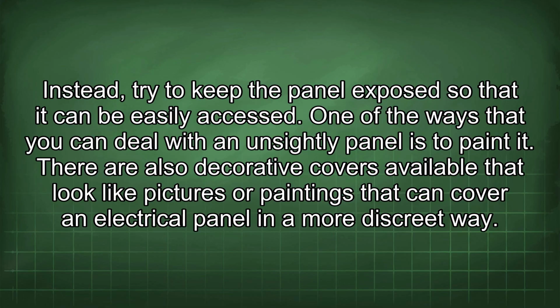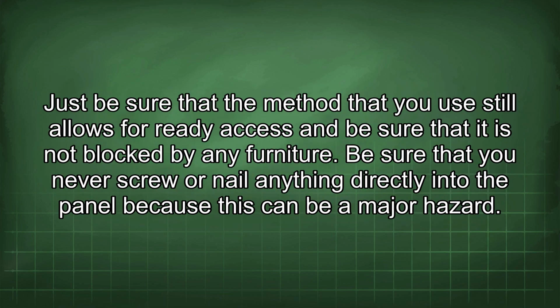One of the ways that you can deal with an unsightly panel is to paint it. There are also decorative covers available that look like pictures or paintings that can cover an electrical panel in a more discreet way. Just be sure that the method that you use still allows for ready access, and be sure that it is not blocked by any furniture. Be sure that you never screw or nail anything directly into the panel, because this can be a major hazard.